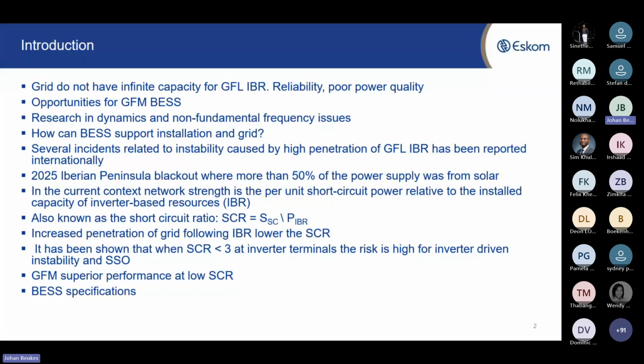So in the current context, network strength is the per unit short circuit power related to the installed capacity of inverter-based resources. So that can be the combined capacity as well. So we can easily calculate the short circuit power at a specific point on the grid, and then we can look at what we install, but we also need to take into account everything else that's installed close by in terms of inverter-based resources to see whether we still have a reliable network. And this is also known as a short circuit ratio. So that equation is very important. It's the short circuit power divided by the combined P of inverter-based resources at a specific location.